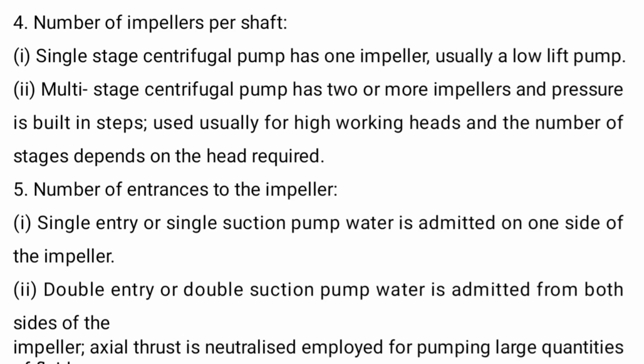The number of entrances of the impeller. In a single entry or single suction pump, water is admitted on one side of the impeller. In a double entry or double suction pump, water is admitted from both sides of the impeller. Axial thrust is balanced, and it is employed for pumping large quantities.